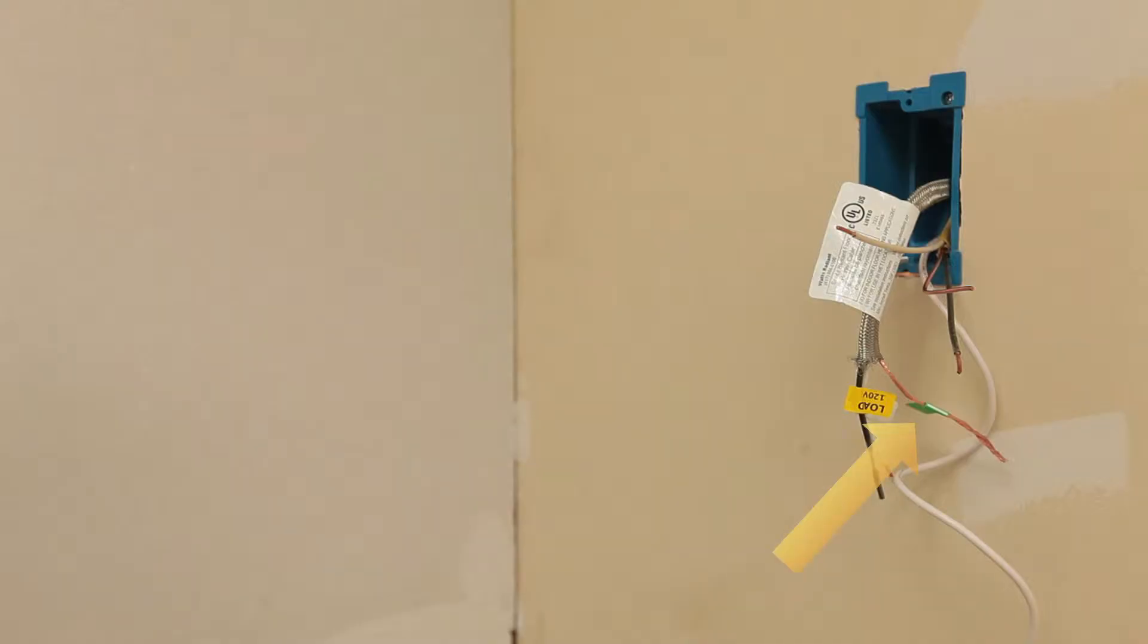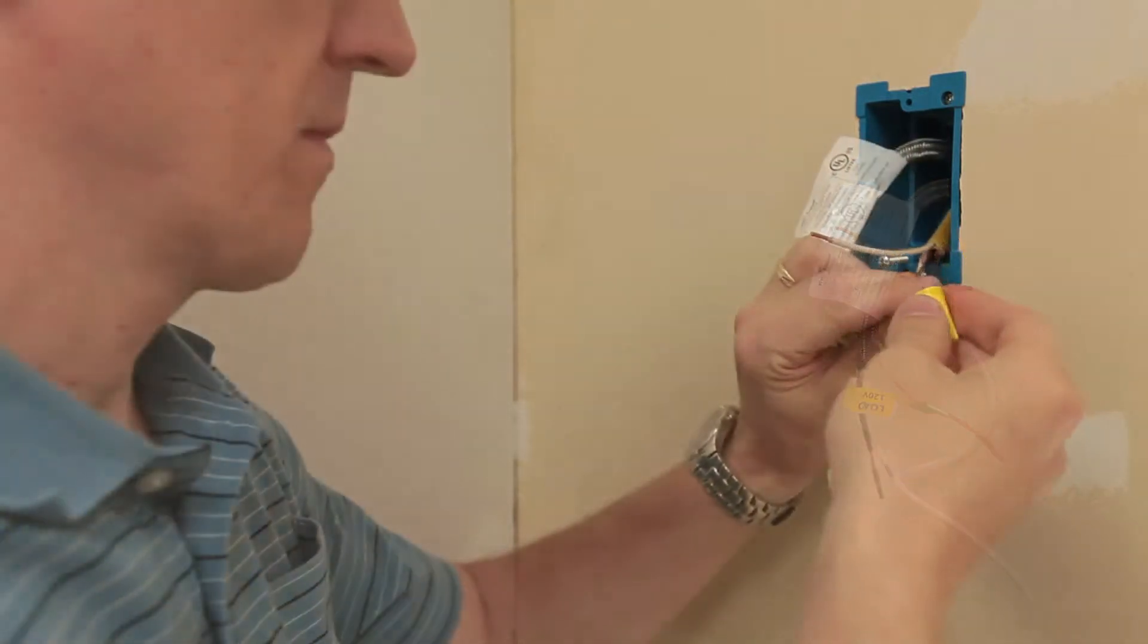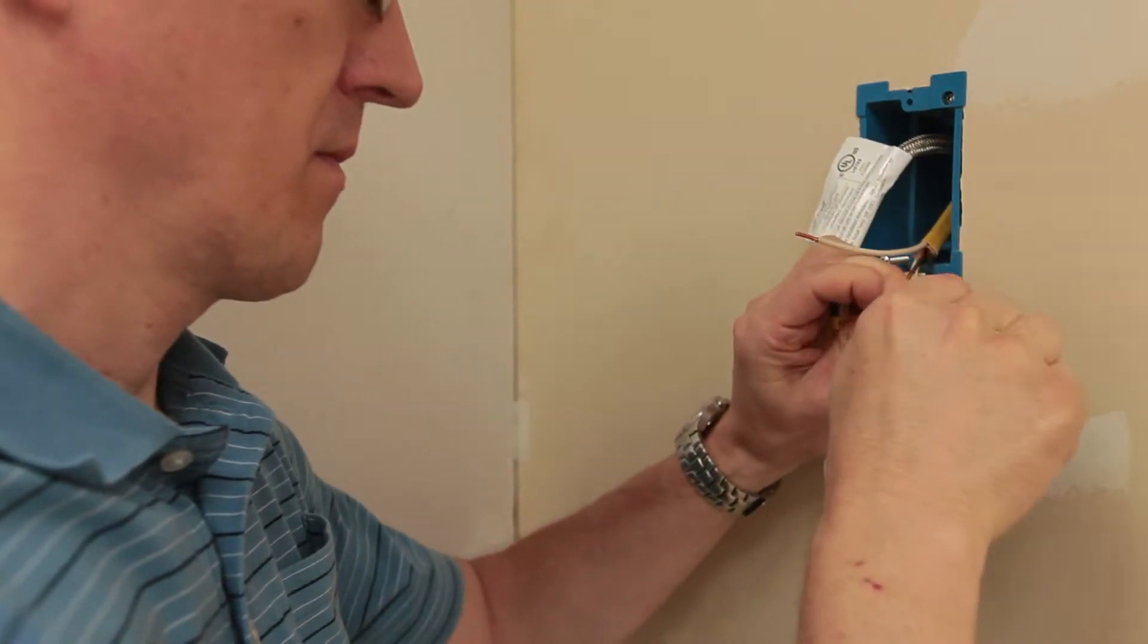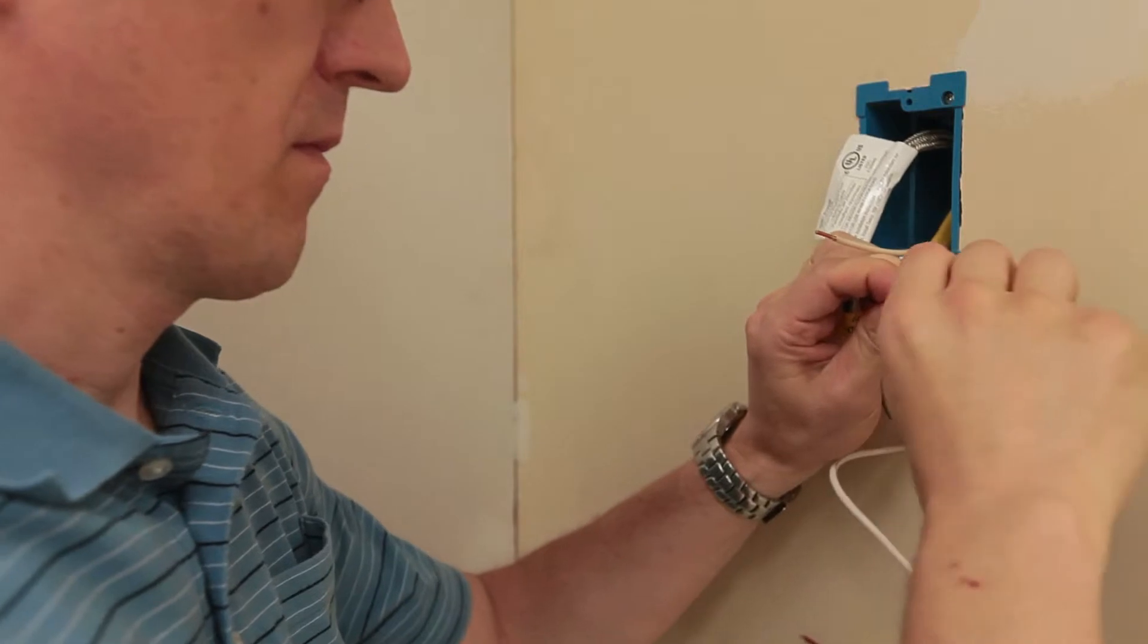Begin by connecting the ground wires from the warm wire leads to the house ground with a wire nut. If a steel box was used, this should also include a short wire to the electrical box grounding screw.